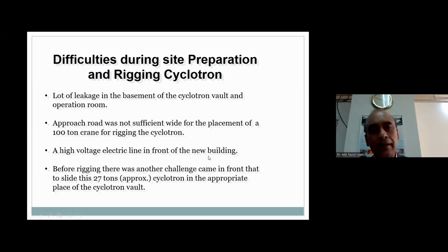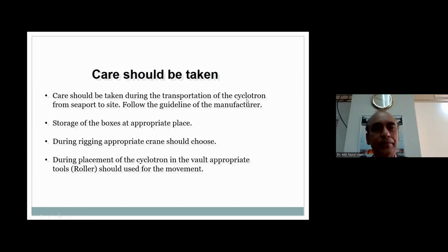Another difficulty was a high voltage electric line in front of the new building. That is an 11,000 volt line that was going in front of this building. Before rigging, another challenge came in front of us: sliding the 27-ton cyclotron into the appropriate place in the cyclotron vault, because this needs rollers or tools for the placement. Care should be taken during the transportation of the cyclotron from the seaport to the site. Follow the guideline of the manufacturer if they have one, and take care of the storage of the boxes of the cyclotron at an appropriate place. During the rigging, an appropriate crane should be chosen. During the placement of the cyclotron in the vault, appropriate tools should be used for the movement.